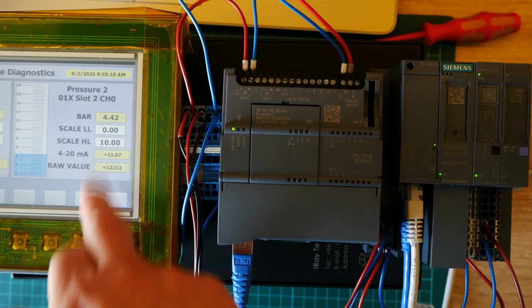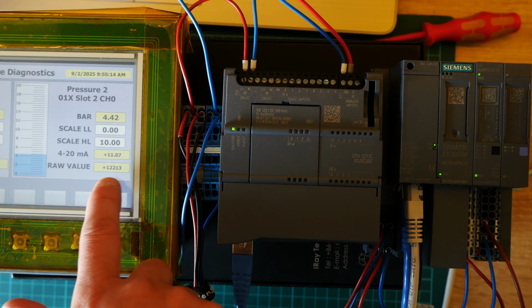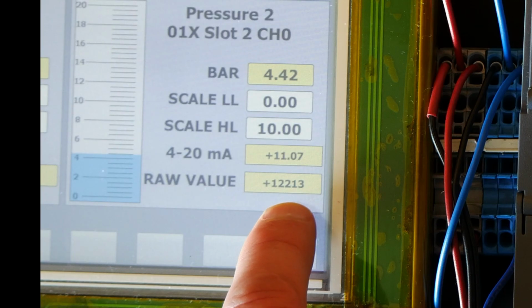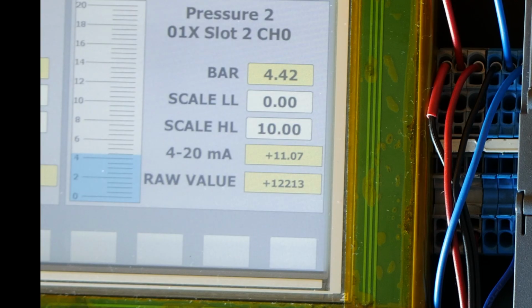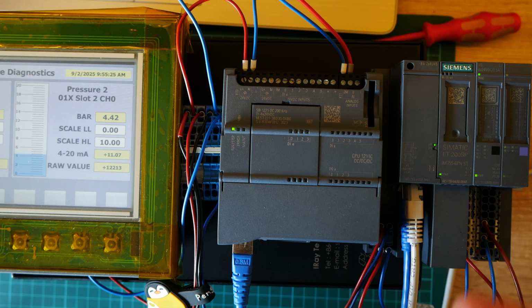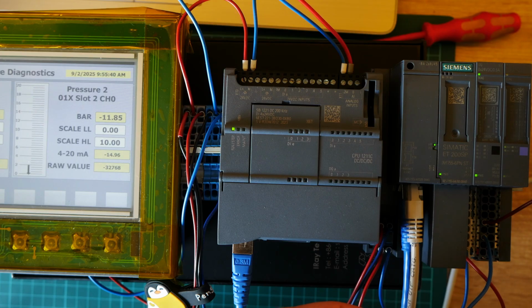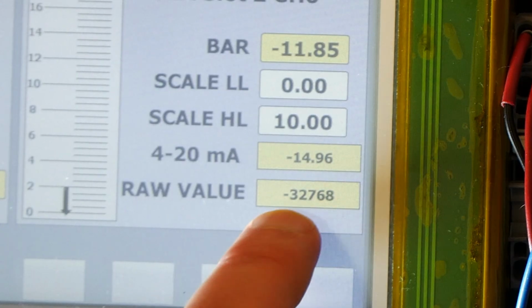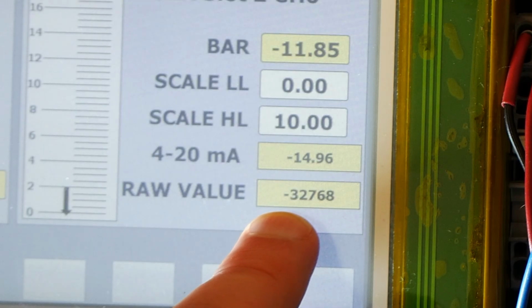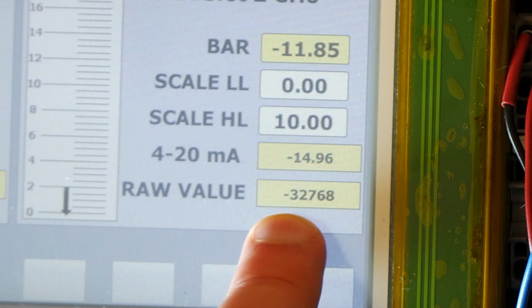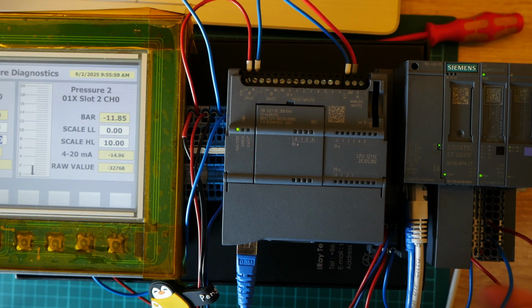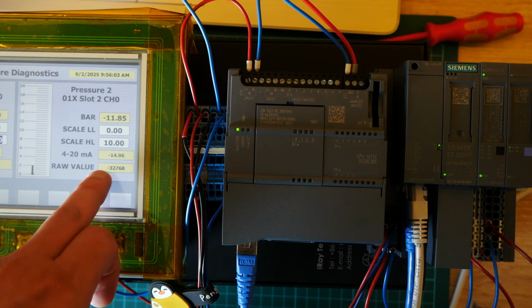Yes, so right now we have some value, and again the raw value is very stable. If this raw value is going up and down like crazy, probably you have a problem with either the analog input card or the transducer. So in that case we open the loop. The loop is open. So the transducer is disconnected right now, and we have a raw value of minus 32,768. So remember that if you have an open loop, then you have this negative value.